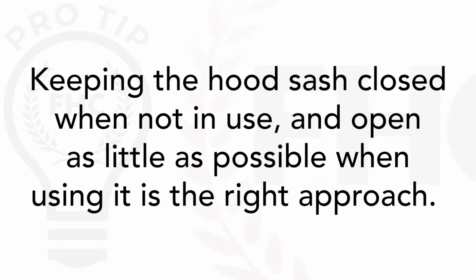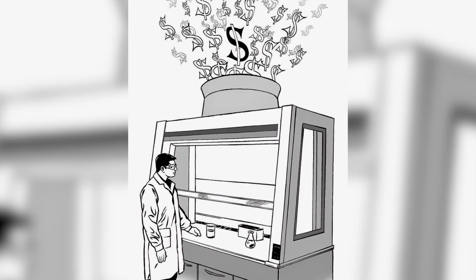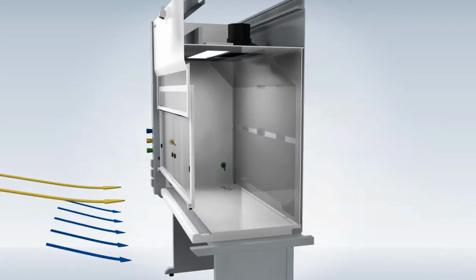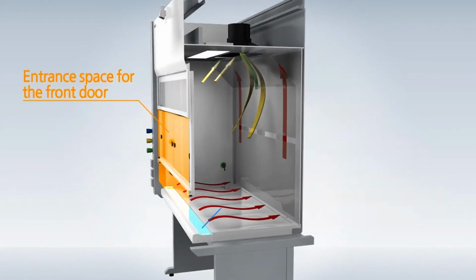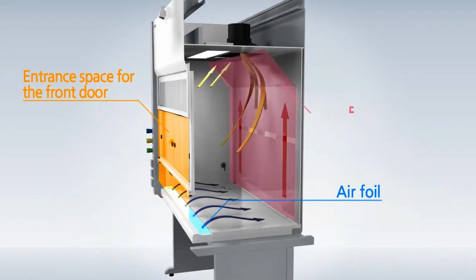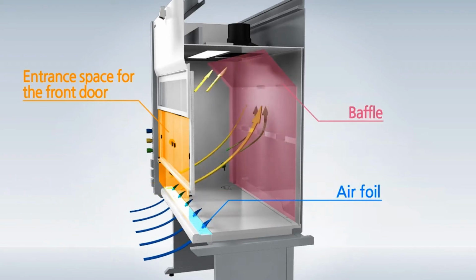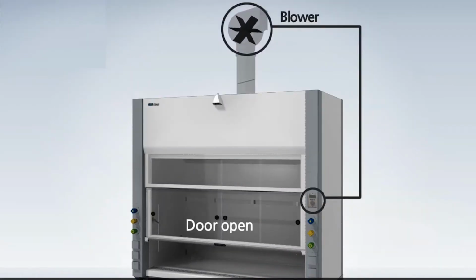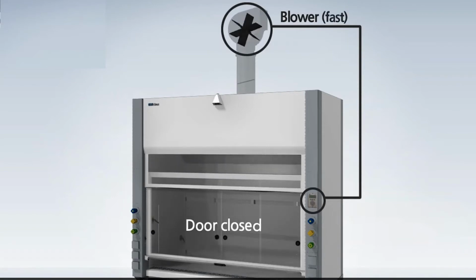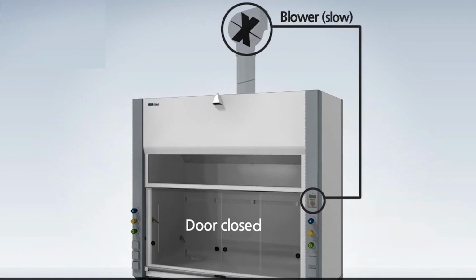But whatever type of sash your hood has, keeping it closed when not in use and open as little as possible when using it is the right approach. The glass is there to protect you from the hazards. Fume hoods are very expensive to operate. They require large amounts of air to function properly. In most modern hoods, the amount of air the fume hood uses is determined by how much the sash is open. The smaller the opening, the less air and energy the fume hood will use. So generally, a closed sash uses much less air than an open sash.